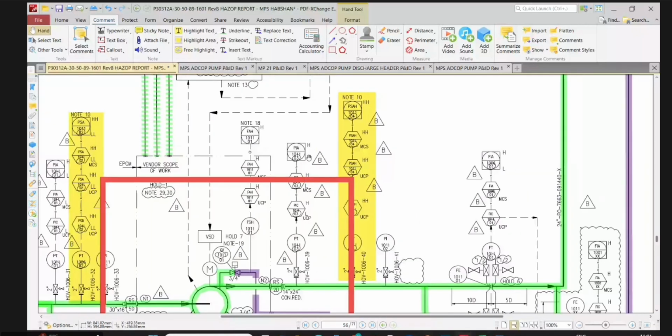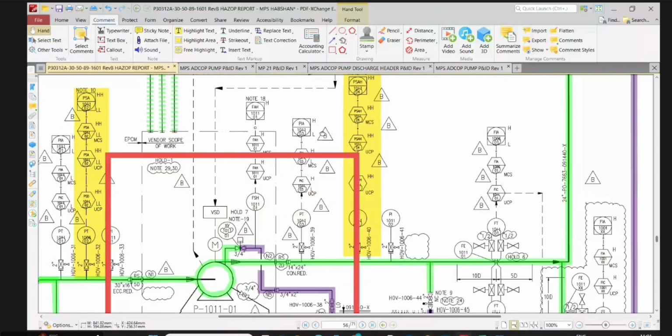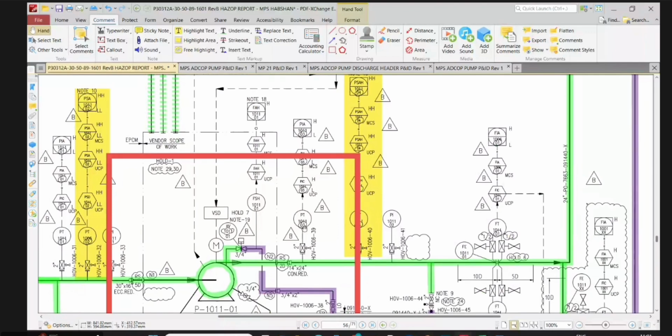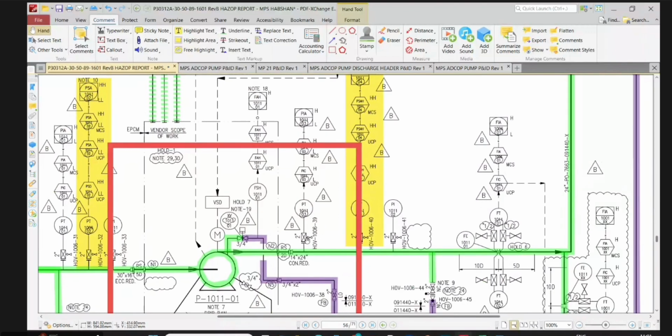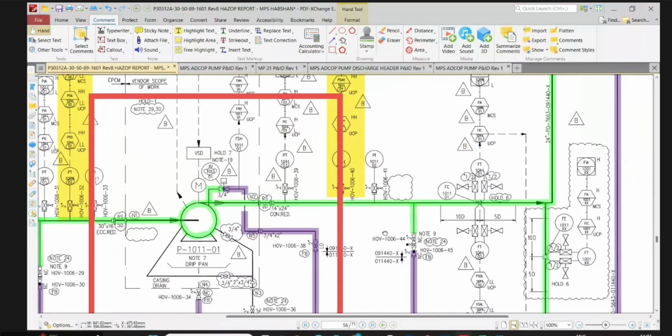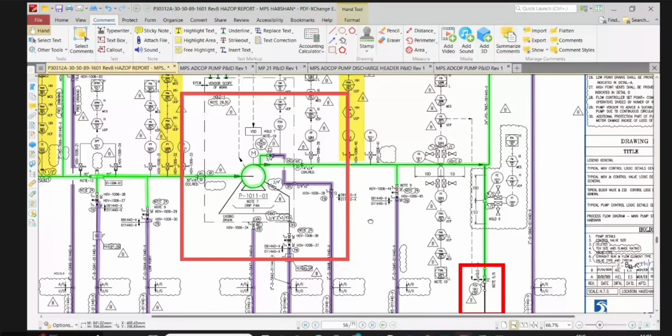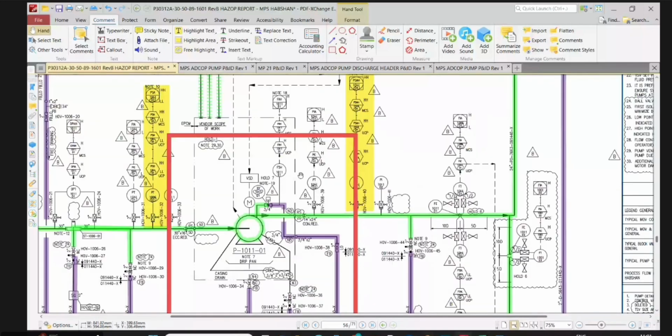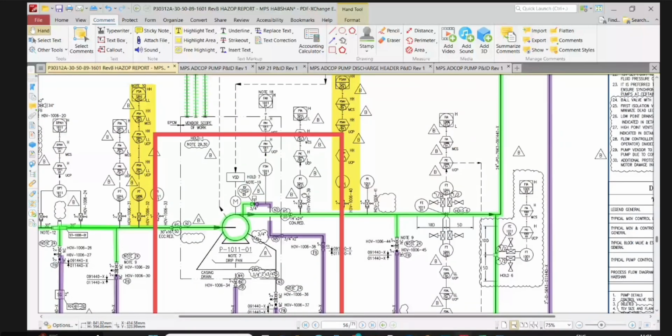PAL, but as the Ananta team is saying, Dilshad, in case of blocked outlet, then it is the pipeline rupture. The pump discharge pressure is higher than the design pressure of the pipe. Sorry, what are you saying? In case of any downstream closure, common MOV closure, then it is mentioned as the piping or pipeline rupture itself.